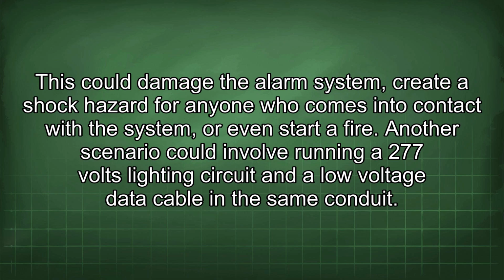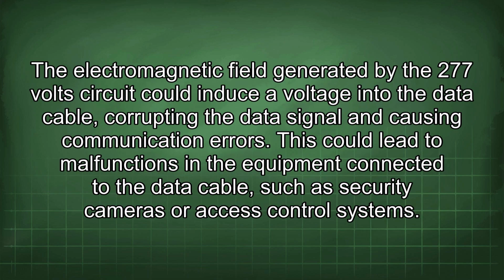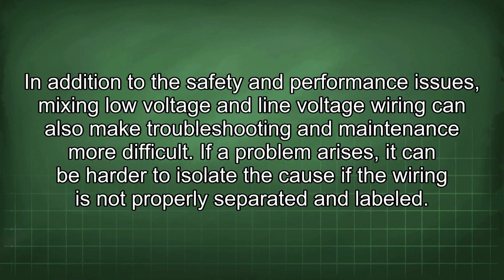Another scenario could involve running a 277 volt lighting circuit and a low voltage data cable in the same conduit. The electromagnetic field generated by the 277 volt circuit could induce a voltage into the data cable, corrupting the data signal and causing communication errors. This could lead to malfunctions in the equipment connected to the data cable, such as security cameras or access control systems.